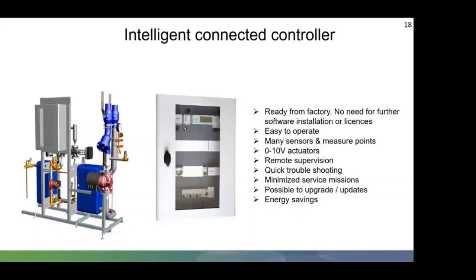By including controls, the substations become a plug-and-play solution, and we're a big advocate of plug-and-play. If the system's been designed properly in the first place, it's a case of delivered to site, plumbed in, connected, and it works first time, other than commissioning. The manufacturer of the substation can support the customer's contracted engineer, reducing the requirements for specialist controls. Again, if it's all built into the control panel, it's a case of just quickly connecting to the BMS system, and off you go.